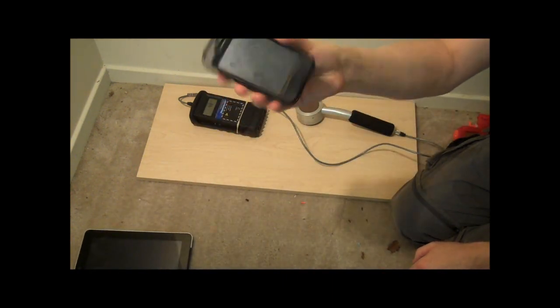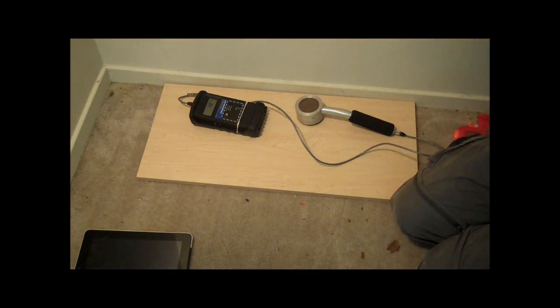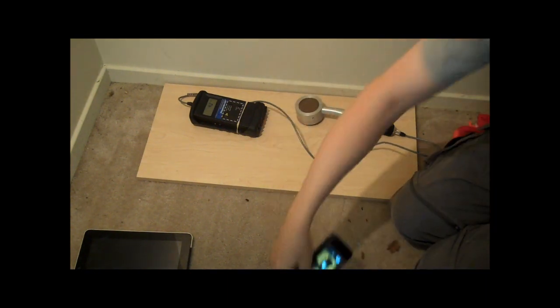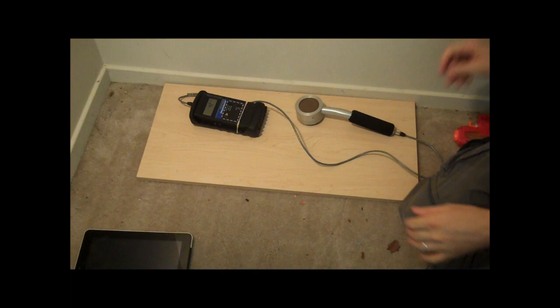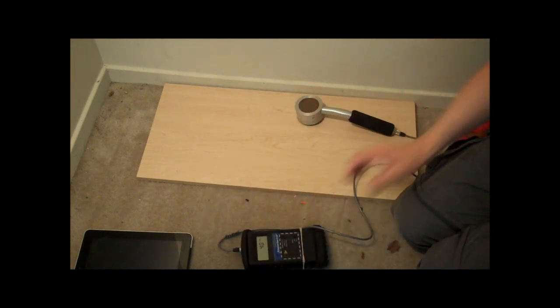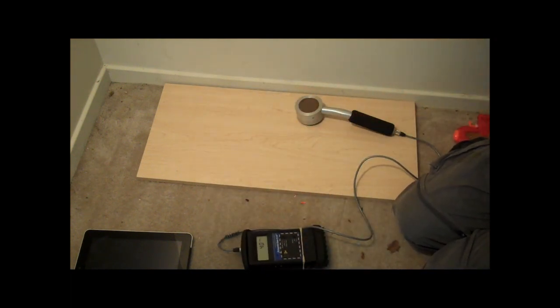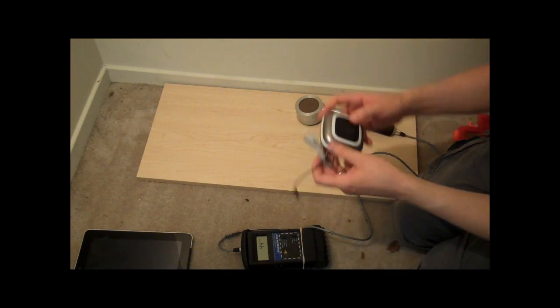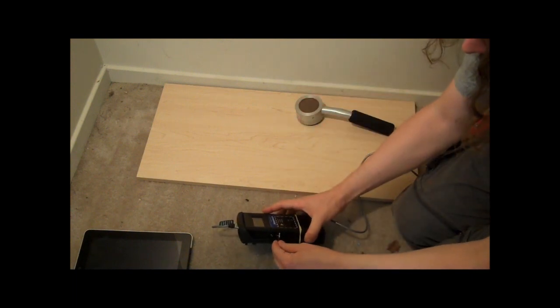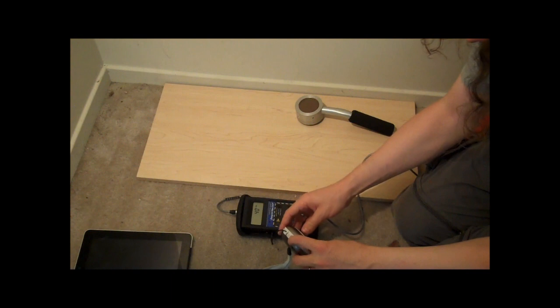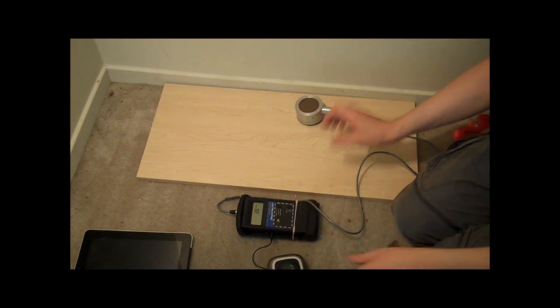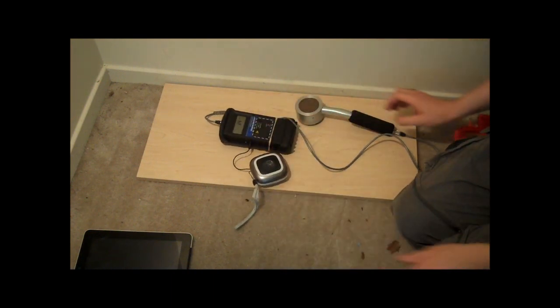Here, actually I have an iPhone here. Let me take my iPhone and move it out of the way so that it doesn't interfere with the test. The first part of the test is to show you the testing area and that it's clean and free of anything that would cause any troubles. Here is my external sounder. I'll plug it up, turn it on. It will produce an audible tick every time radiation is detected.